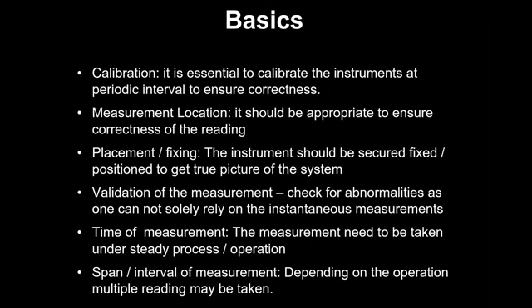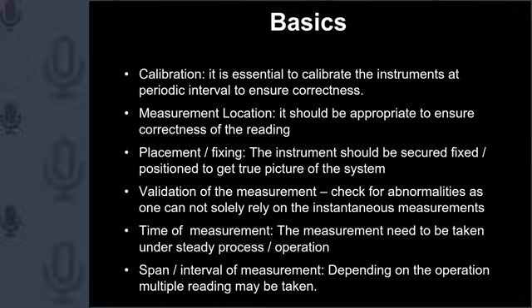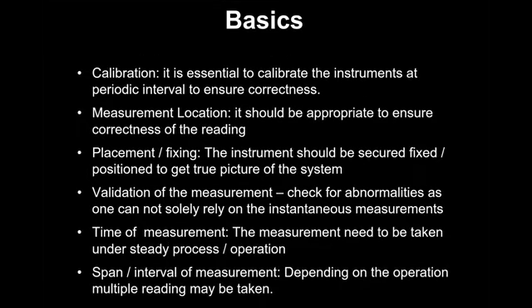So there is an internal refractory on the duct. The duct will be refractory lined. Inside the duct there is a refractory lining, then there is a casing, and after that there is some small insulation, which should not have been there, but they had it. So we tried to take the measurement, but we were not getting any reading. When I went there to see, I saw that it had a refractory lining of maybe 200 mm or so, and we had a short length probe.